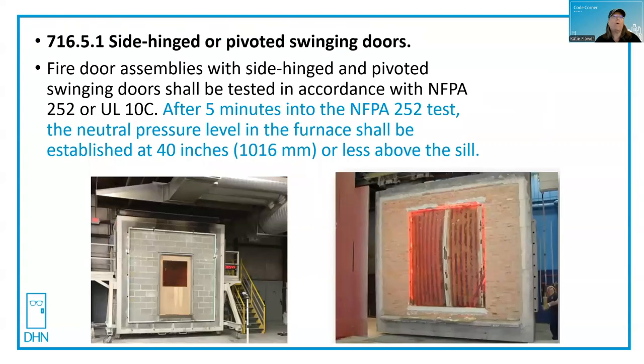Where is it required? The 2018 and similar editions of the IBC, the International Building Code, tell us that fire door assemblies that are side-hinged and pivoted swinging doors shall be tested in accordance with NFPA 252 or UL 10C. And UL 10C is positive pressure.